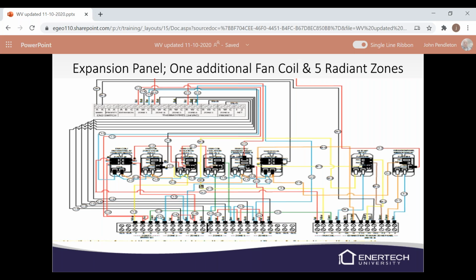This is the expansion panel. So if you have, let's say, you already have a fan coil and 5 radiant zones, but you have an additional fan coil and 5 radiant zones, you can add this expansion panel on and you're able to handle those needs. One thing I do want to say, I don't really care how many zones that you have. Just remember that if all zones are calling, the unit is either an 040 or an 060, so it can only produce 3.5 tons or 5 tons. If you have 10 zones and that takes 10 tons and they're all calling, the unit is never going to be able to handle it. So just because it can take 10 zones doesn't mean that it should. You just have to remember it's a 5-ton unit or a 3.5-ton unit, and keep that in mind when you're putting out these different zoning needs.